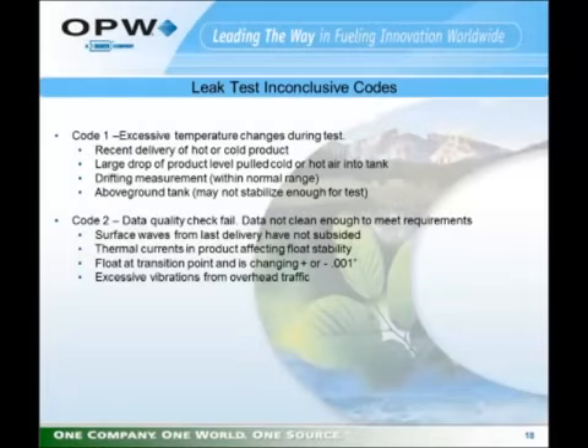Leak test inconclusive codes. Code 1 is excessive temperature changes during the test. This could be due to recent delivery of hot or cold product, or a large pumping of product drew a large amount of hot or cold air into the tank, a drifting measurement, or an above ground tank. Now, above ground tanks cannot be tested because the temperature is never stable enough to perform a valid test. Code 2 inconclusive is data quality check fail. That just means that the data is not sufficient for the test. This can be caused by surface waves, thermal currents, a float that's at a transition point, or excessive vibrations from overhead traffic.